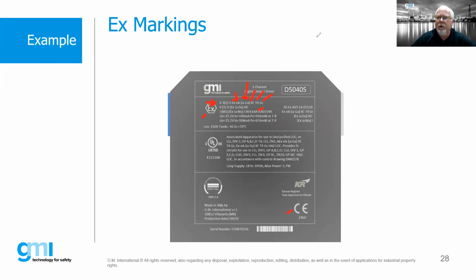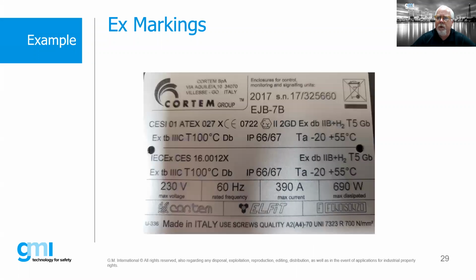So let's clear that one, and then we'll look at another label. So this is an example of a label of a flame-proof enclosure. And how I know this is flame-proof? Well, let's see. I can show you a little bit here. Here's our protection concept, EXDB. The old legacy would be marked EXD, but that's now changed to DB. So here's our ATEX certificate, what you see here. We see our little CE mark here. We should find, and there it is, our little EX hexagon. This is telling us the notified body that did the test.